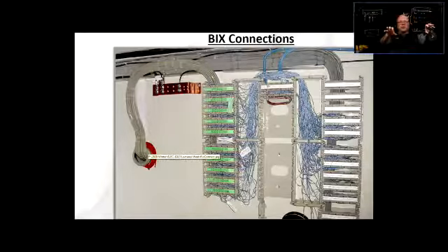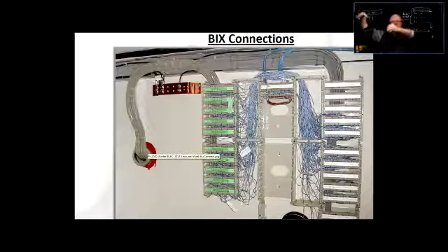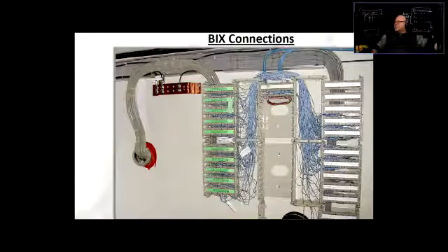Maybe that secondary demarcation point serves the west end of the mall, right? The other demarcation point somewhere there would serve some other area of the mall or whatnot, right? So what do we have here? We have a bunch of telephone lines in the 25 pair cables, and they are terminated on the strips, and these are the BIX strips. And over on the other side, you have the field wiring that is traveling to some other locations.